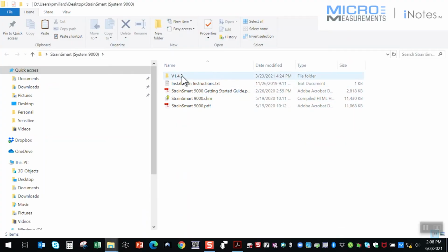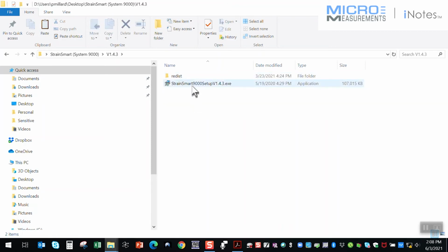So once I've accomplished that, I should be able to then go into my StrainSmart software. And the current version as of the shooting of this video for the System 9000 is version 1.4.3. And I should be able to go in there and install the StrainSmart software. It's not too big of a file, but it takes just a moment to get it installed.